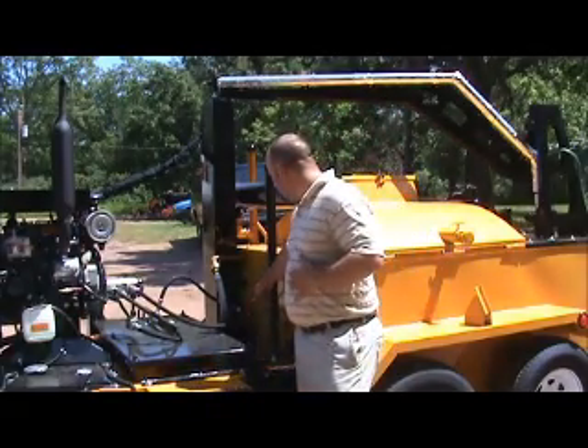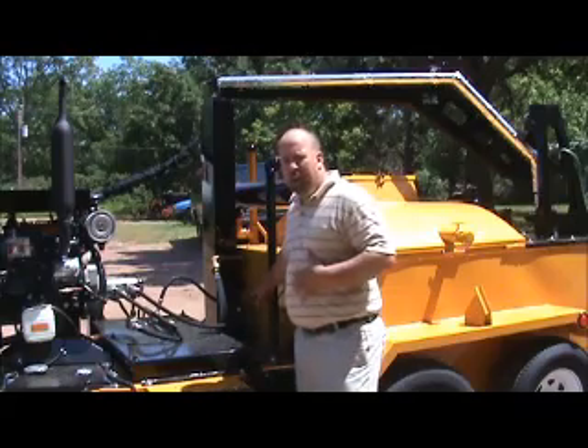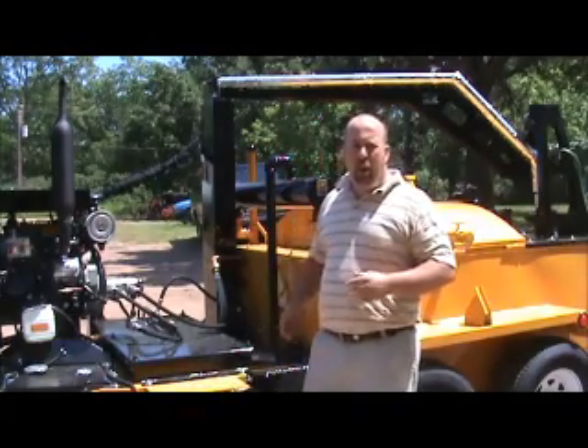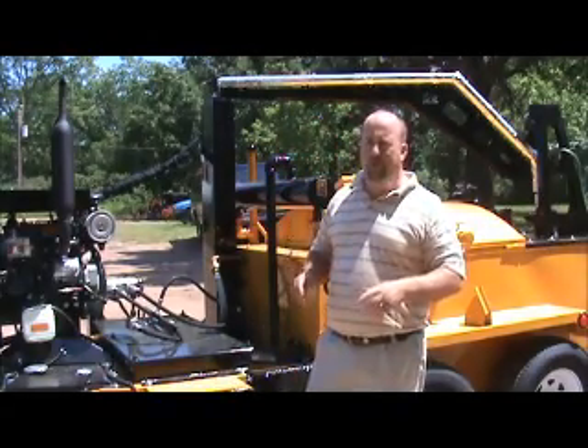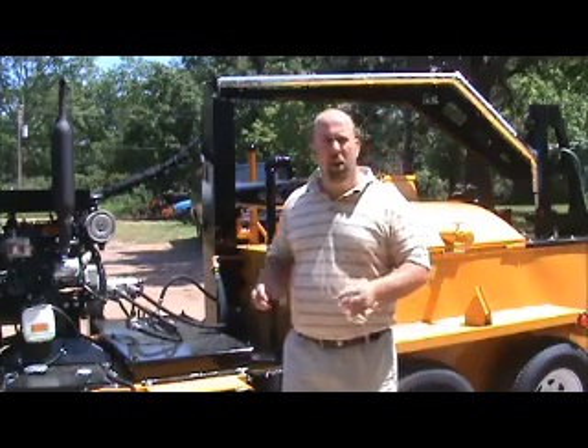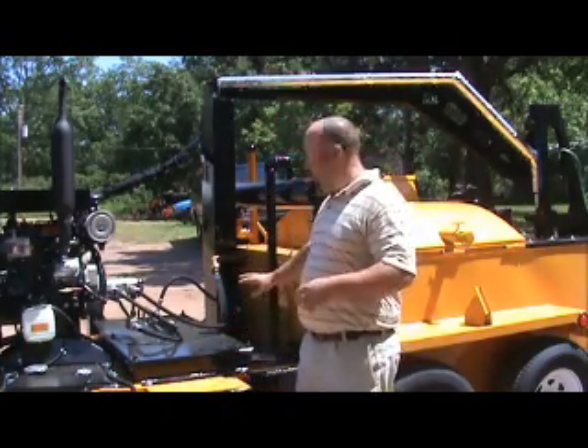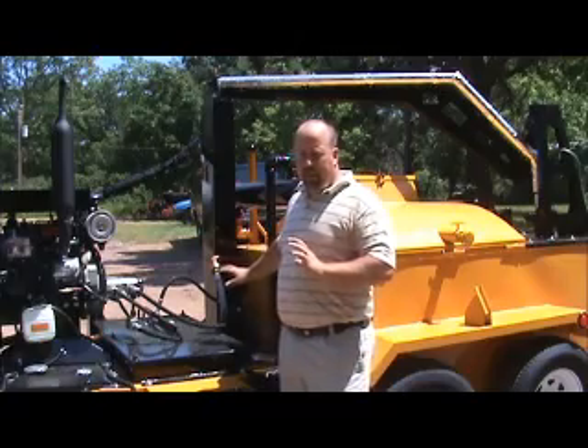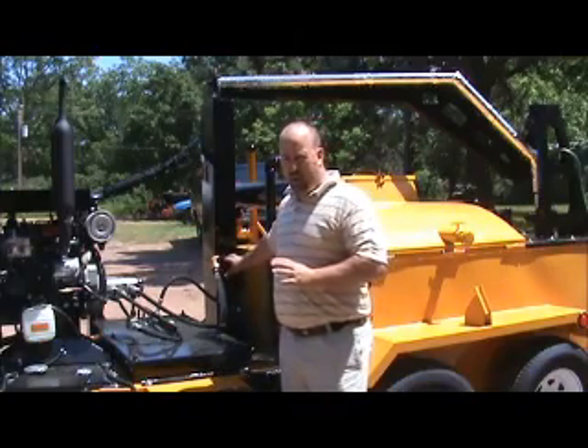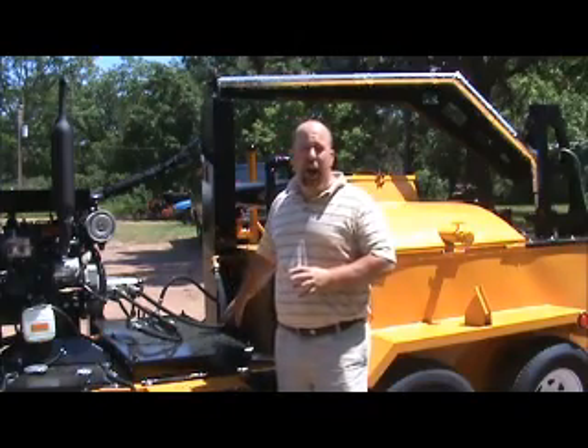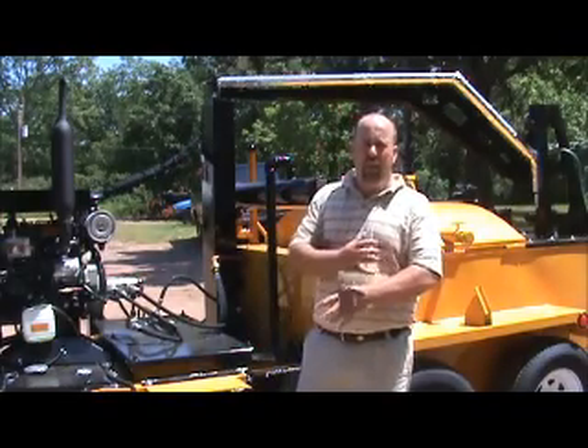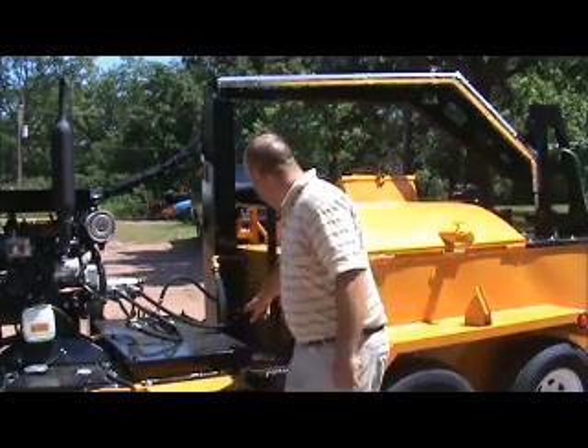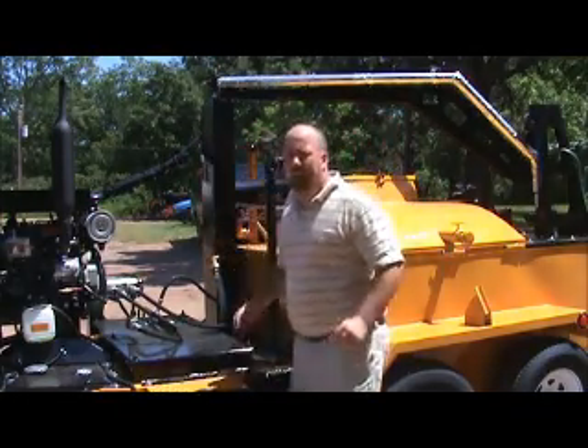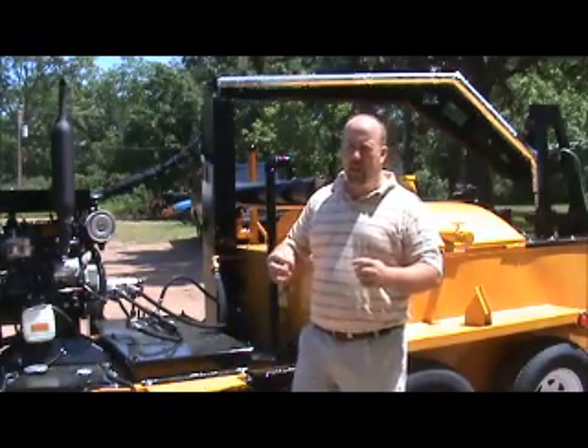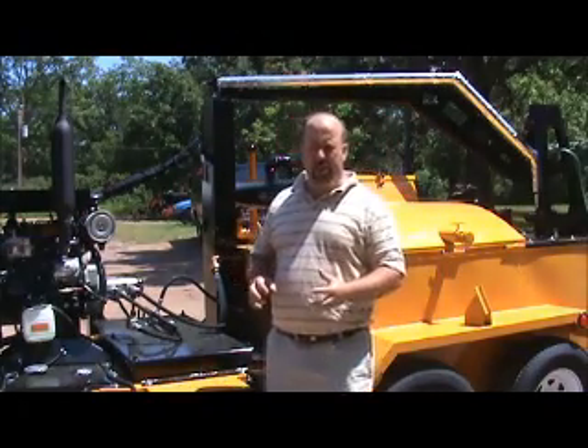There is a maintenance item down there. There's a packing gland on that pump. If you notice the pump starts to drip or leak a little bit of oil, you need to tighten that up. Strong caution is recommended, because all of that pump and those lines are very hot, so make sure that you have heavy gloves and sleeves on when you adjust that. There are 2 nuts on the packing gland. You don't need to crank them down, you just need to snug them up until it stops leaking.